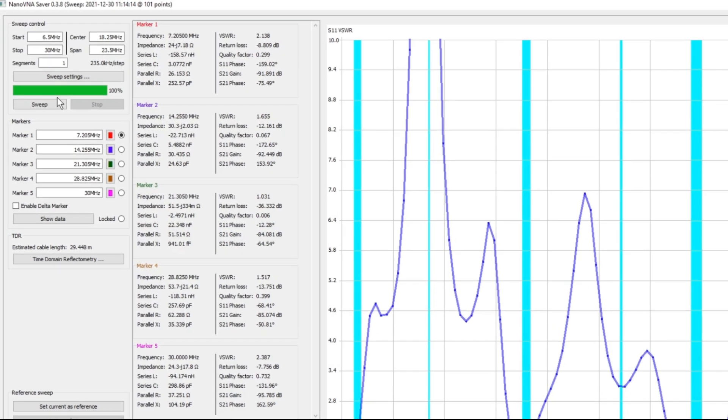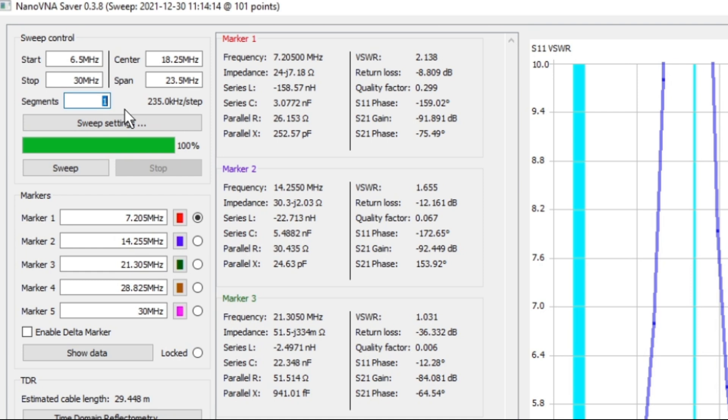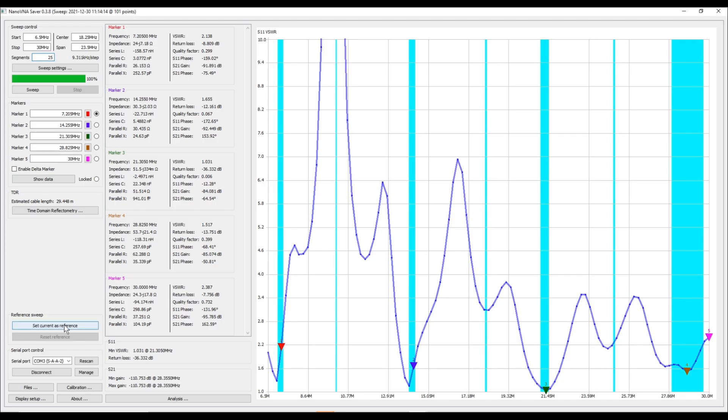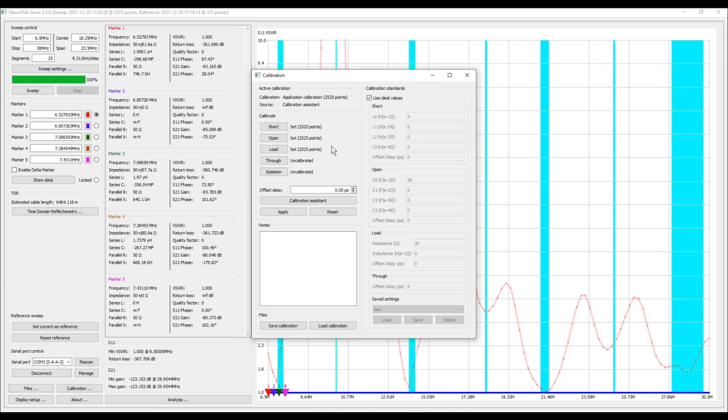Now what I want to do is I'm going to come up here to our sweep control and I'm going to change our segments from 1 to 25. And when I do that, you can see that now I have 9.311 kilohertz per step as opposed to the 235 kilohertz, and this is going to give us a much more granular reference. I'm going to go ahead and I'm going to set this as my current reference, and then when we do our next sweep it will overlay on top of this reading. Okay, so after running the calibration, you can see here my short is set at 2525 points, as are all the other calibrations, and that is significantly higher than what we had before at 101 points.